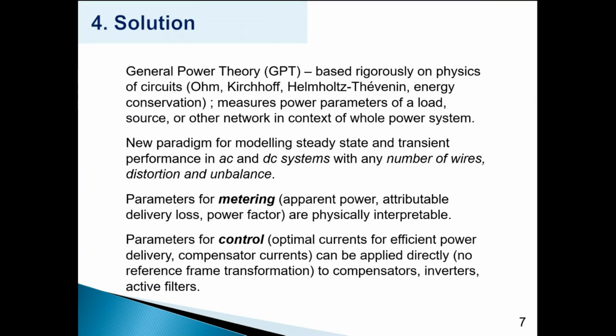It's based on the physics of circuits, names you'll recognize: Ohm, Kirchhoff, Helmholtz, or Thevenin, depending on whether you come from a German or a French background. Energy, the law of energy conservation, and it measures the power parameters of a load, source or network in the context of the whole power system: the source, the equivalent delivery system, and the apparatus. So it's a completely new paradigm for modeling steady state and transient performance in AC and DC systems with any number of wires, with distortion and with unbalance. And it leads to parameters for metering, including apparent power and attributable delivery loss and power factor, and parameters for control. That includes things like the efficient power delivery, compensation currents, and in control of compensators and inverters, and it doesn't require reference frame transformation. We'll come to that again later.